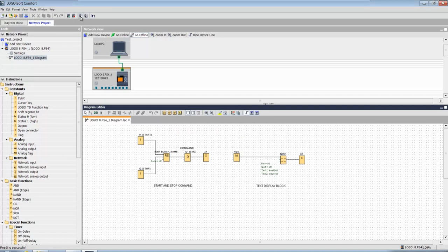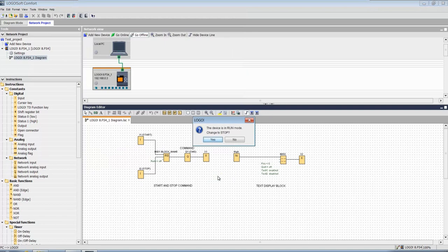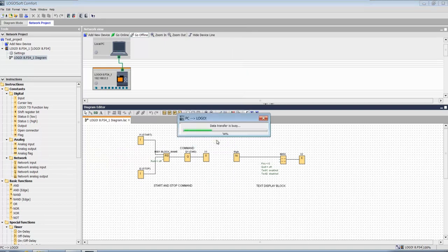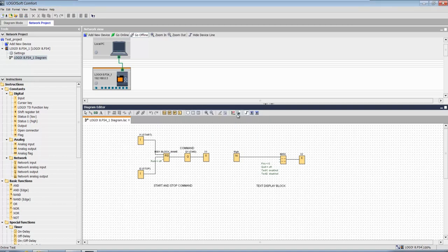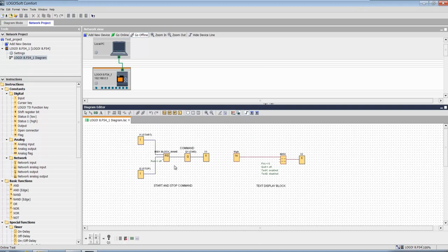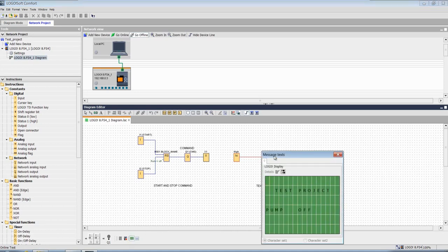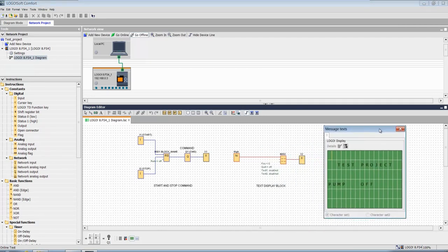Now let's download to our PLC. Connection is okay. It will put your controller in the stop mode. Even a small change you want to make, download will always stop your Logo PLC.